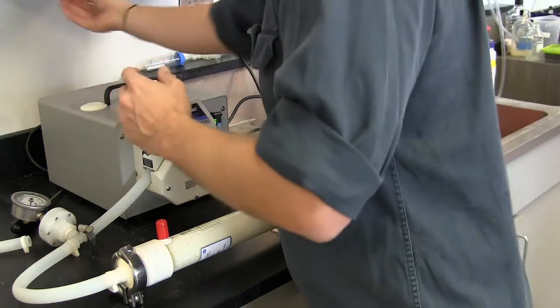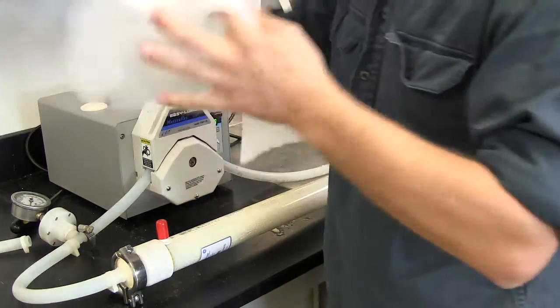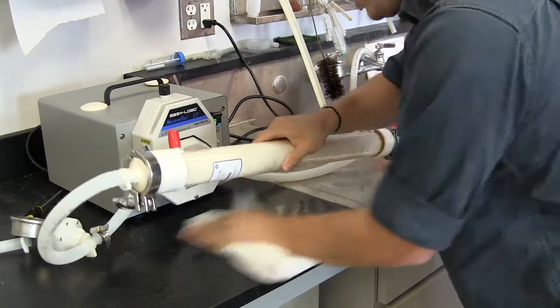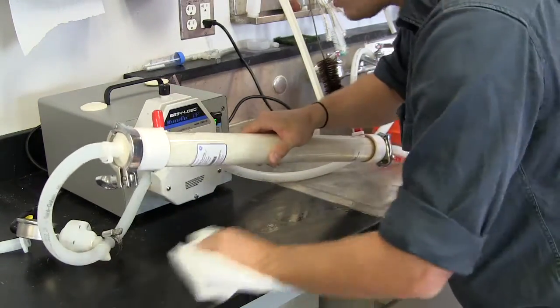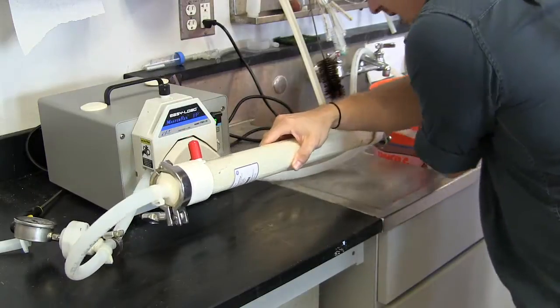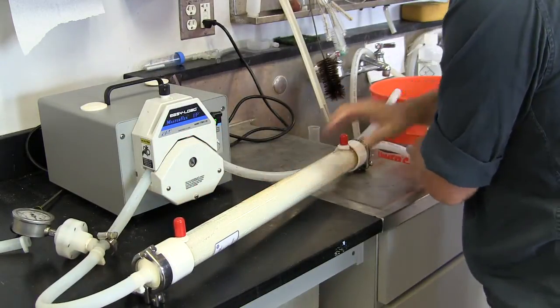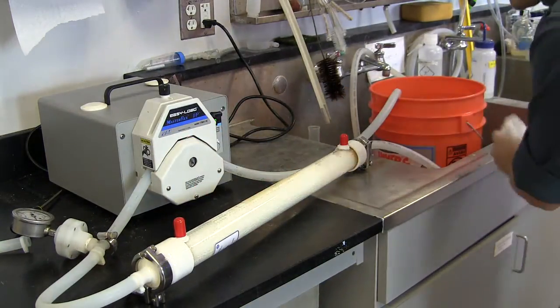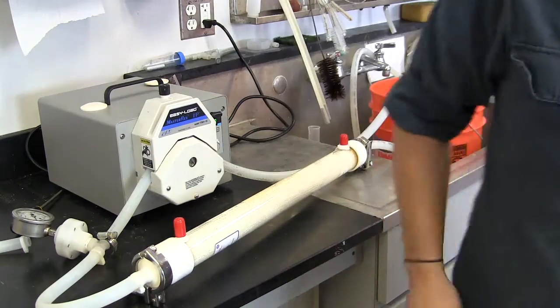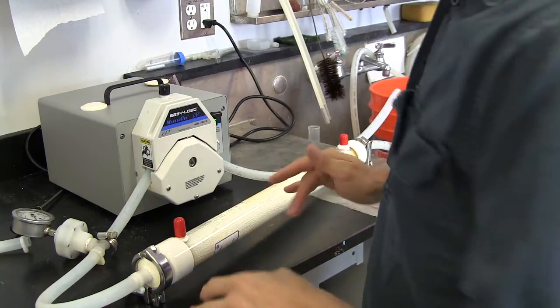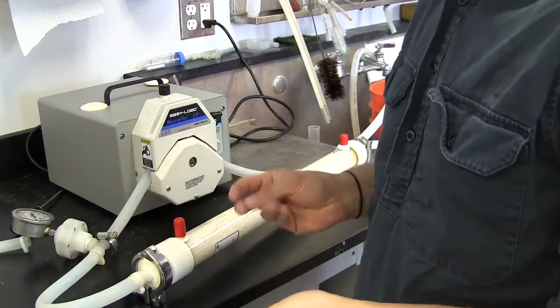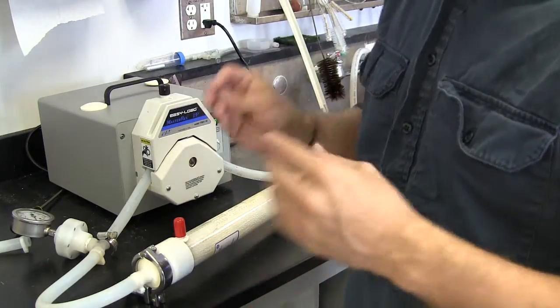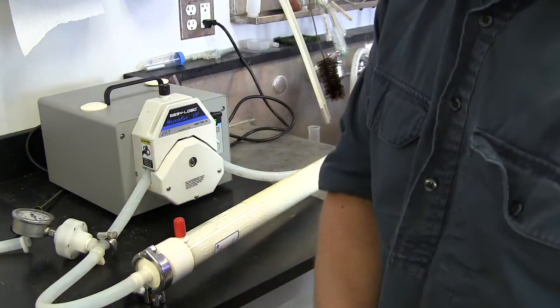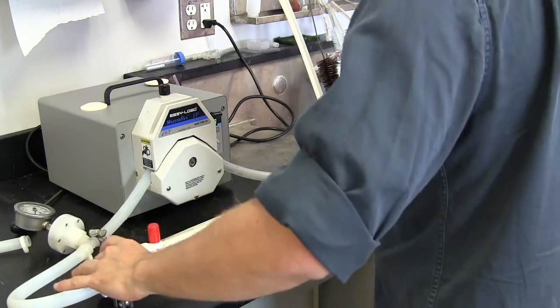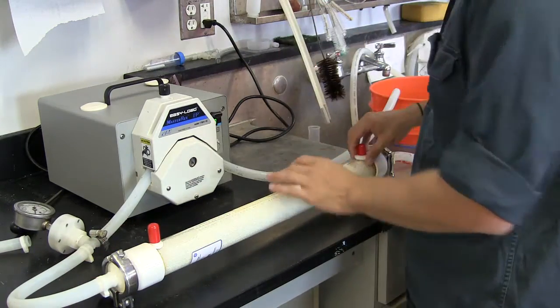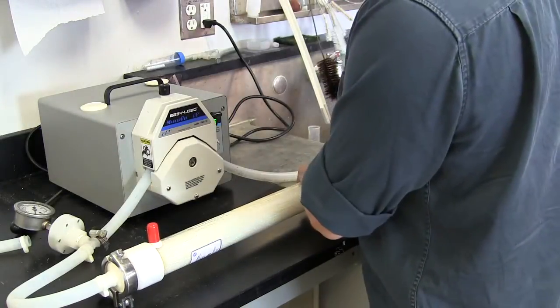What you then want to do when you're setting up your TFF is dry underneath it. Dry everywhere you can where liquid could come from, because if you have a leak in your TFF, you want to know about it as soon as possible. When you're first concentrating your sample and you lose some liquid, it's not a big deal. But once you've concentrated 60 liters down to 1 liter, if you lose 10 mils, you're losing a lot of equivalent volume of seawater. So make sure it's nice and dry under there so you can, as soon as possible, see any leaks that you may have.